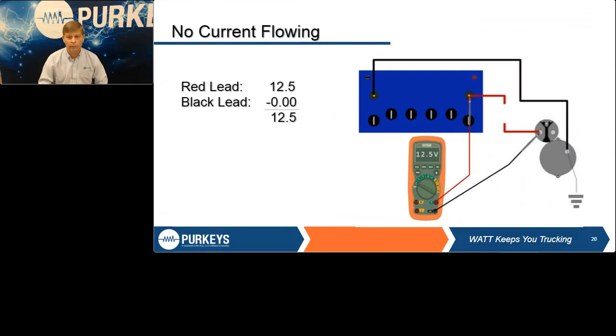The answer is the cable's open, it's got a break in it or whatever. Even if just one single strand was still there, this wouldn't happen, so it has to be a complete break. It could be a tripped circuit breaker, a blown fuse, something, but there's a complete open in that circuit. This will generally never happen on a starter because of the size of the cable, but the same rules apply for any type of circuit you're troubleshooting.